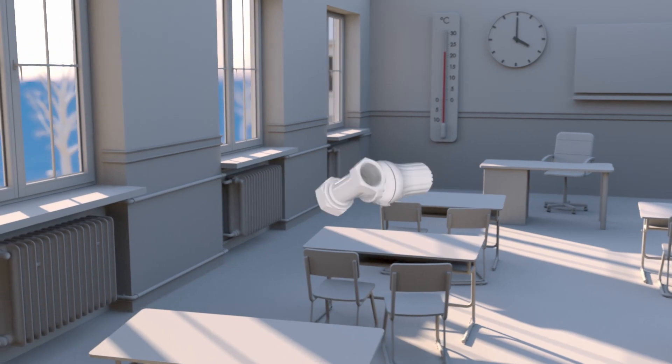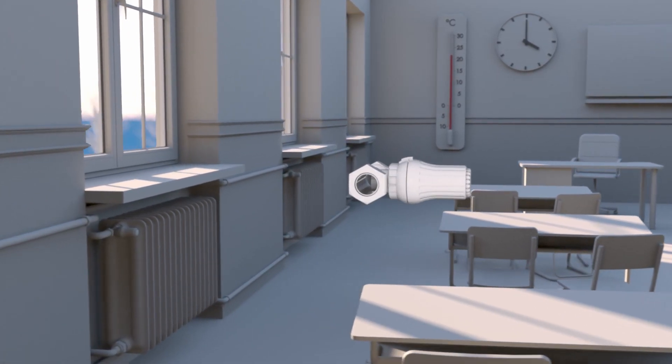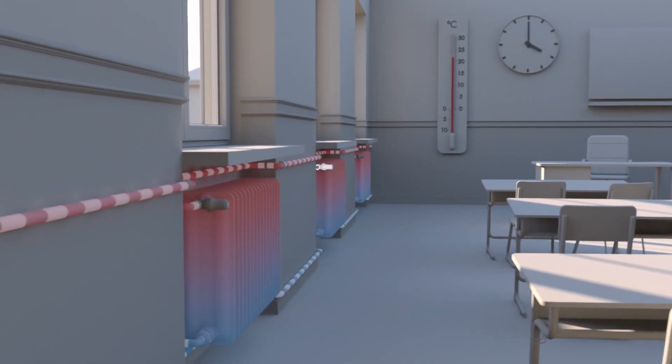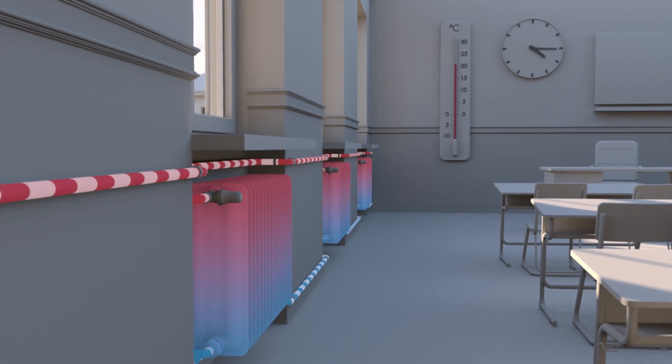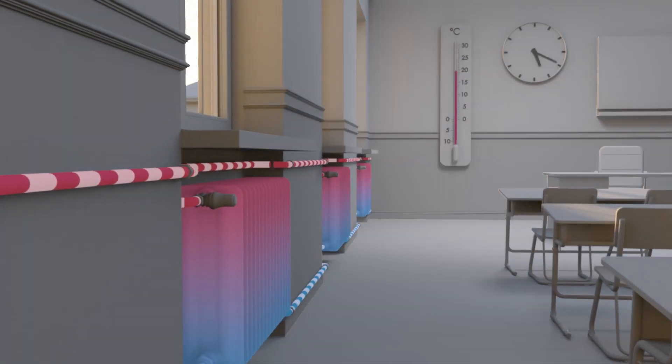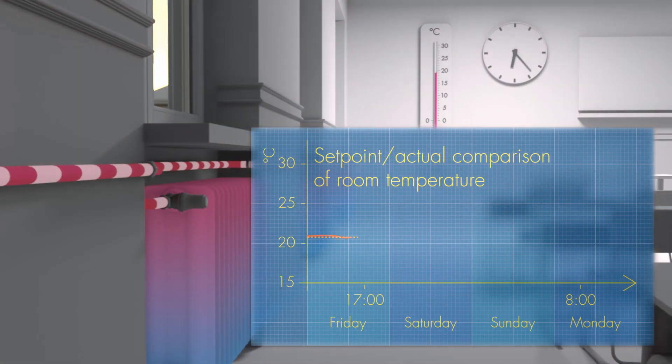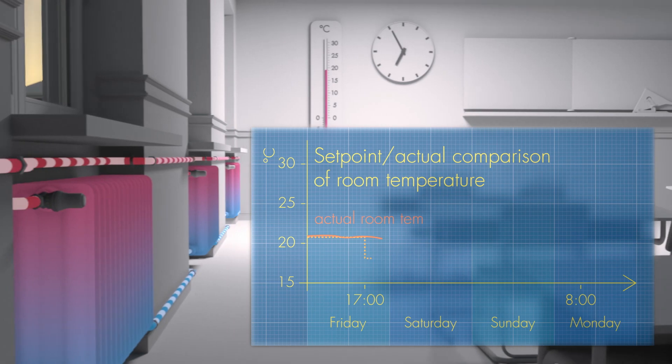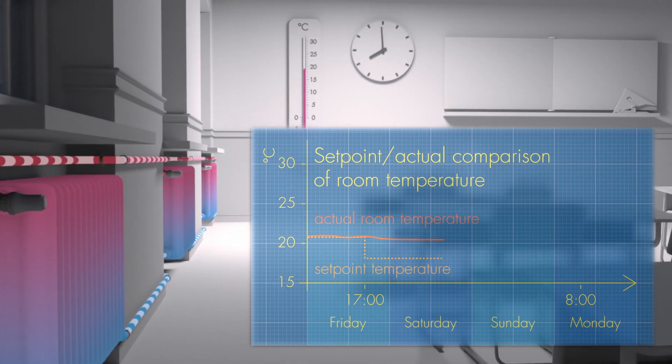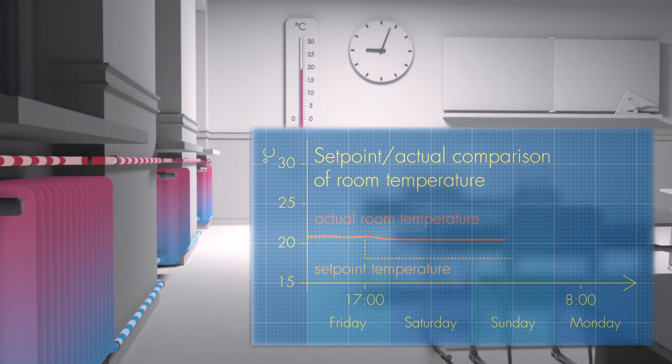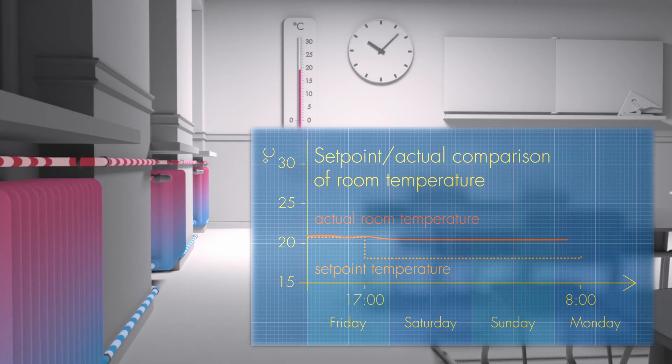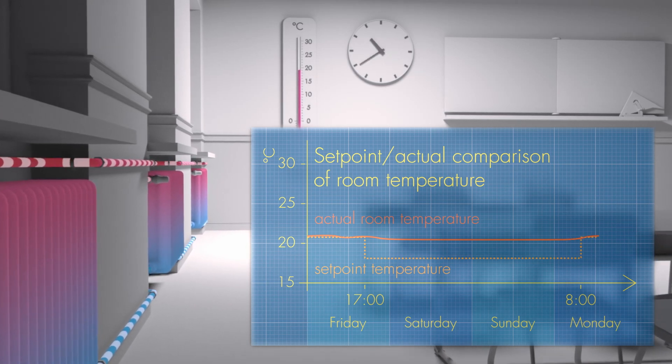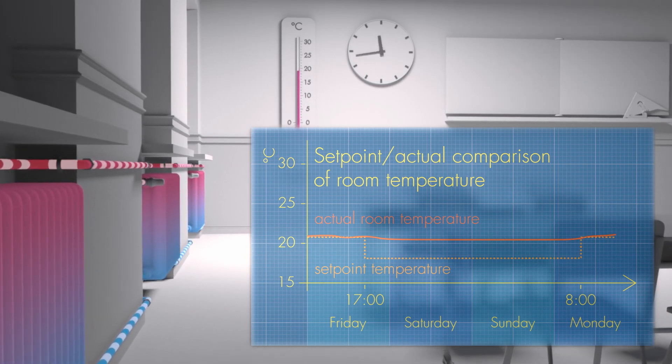However, the thermostatic valves work against this. They open the radiator valves in response to the slight decrease in room temperature. The flow rate in the radiators increases to prevent a further drop in the room temperature. But this also prevents the setpoint temperature for the setback mode from being reached.